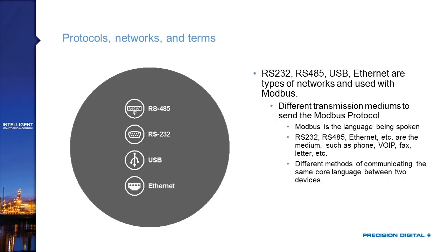Now let's look at protocols, networks, and terminology you'll hear when talking Modbus. Modbus sends digital communications — bits packaged into Modbus packets — but the question is how does one device actually send information to another? Since Modbus is an application-level protocol, it's about how zeros and ones get read, not how they get transmitted physically. The most common physical networks in the process industry are RS-232, RS-485, USB, and Ethernet.